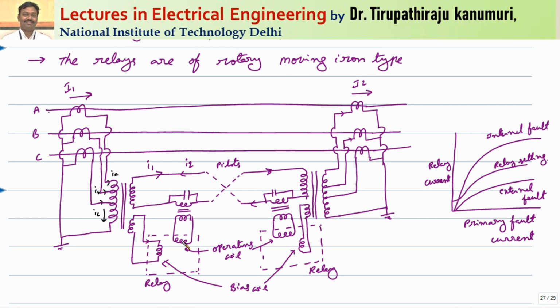So let us take the case of some internal fault. Whenever some internal fault happens here, the current I1 is greater than I2, agree with me? When I1 is greater than I2, the current will circulate in this coil and accordingly induce in the secondary, so your relay will operate. I am repeating once again: for internal faults, as the currents are different, the EMFs induced in the secondary are different, and because of this difference in voltages, the current will circulate depending on which primary current is greater.